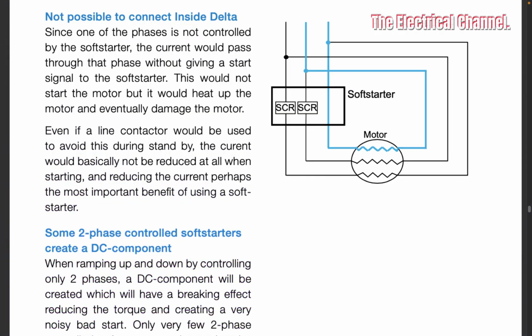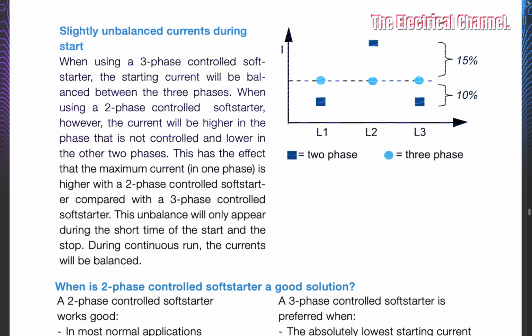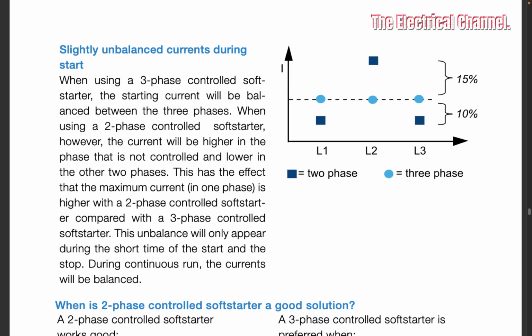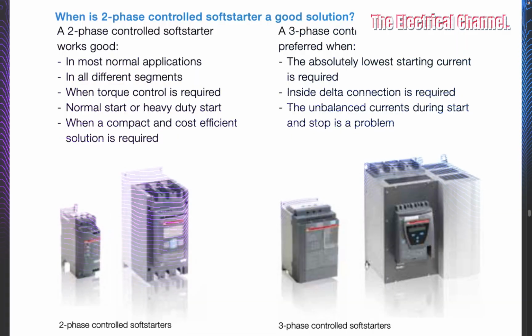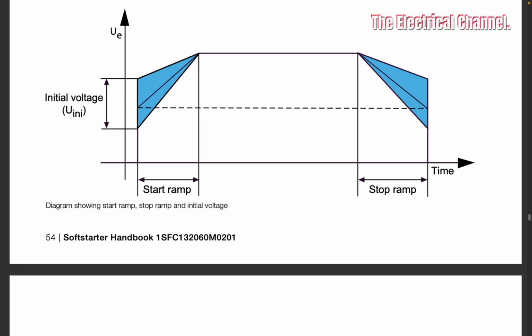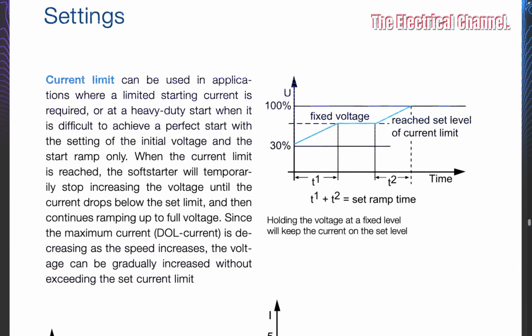It is more and more common to offer integrated bypass contacts in the main circuit, minimizing the power loss in normal operation. Depending on the model of the soft starter, it can be equipped with a built-in electronic overload relay, eliminating the need for an external relay, PTC input, fieldbus communication possibilities also, and more.